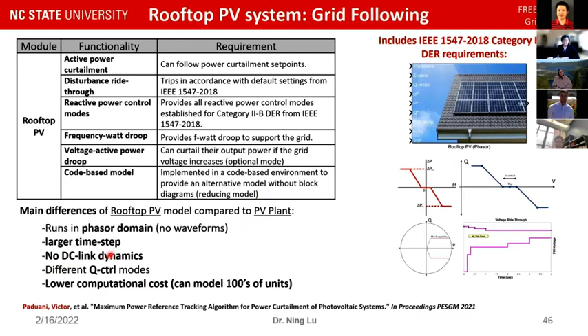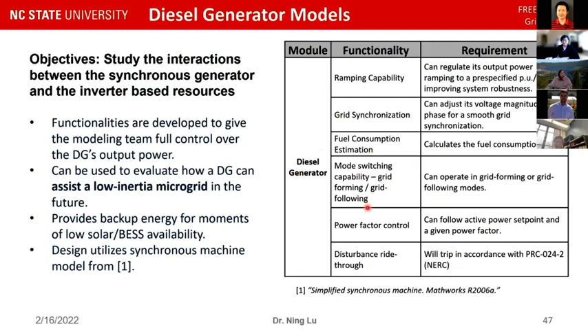We also model the diesel generators. The reason we do that is because we want to study the interaction between synchronous generators and inverter-based resources. Diesel generators in a microgrid could be valuable to try to provide a little bit of inertia to the whole operation, because mainly if you have a PV powered system, you only have battery storage and PV systems. If we do have a diesel there, we want to see whether or not they will compete with each other, and whether the diesel with its inertia could help, or could compete against the battery control and worsen the situation. That's the main reason we simulate the diesel with these functionalities.